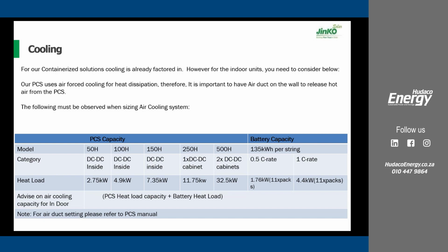Then also for the C rating, for 1C batteries, in a 1C configuration, let's say 500 kilowatts and 500 kilowatt hours, we need to allow around 4.4 kilowatts for each of the battery racks, that is the 135 kilowatt hour ones. So if you're looking at 10, that makes it around 44 kilowatts as well. So you need to make the consideration for that in the configuration. We've only given this as a guideline. Of course, the cooling needs to be specific to the region and also the site conditions.